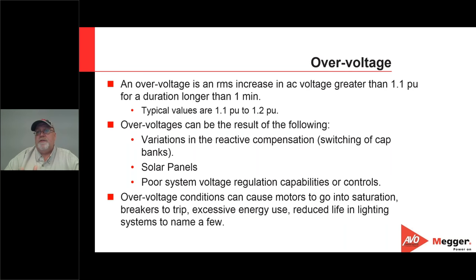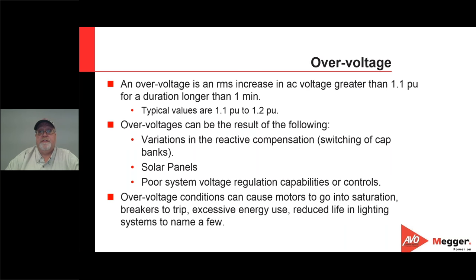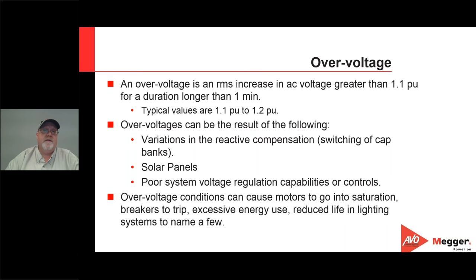What issues can over voltages cause? To be blunt, you can trip a breaker, see excessive energy use on resistive devices, reduced life in lighting, and with motors you can get core saturation. If motors go into core saturation, you'll again get into overheating situations.